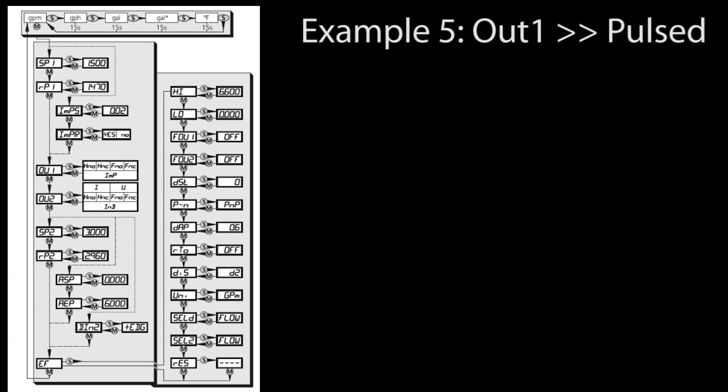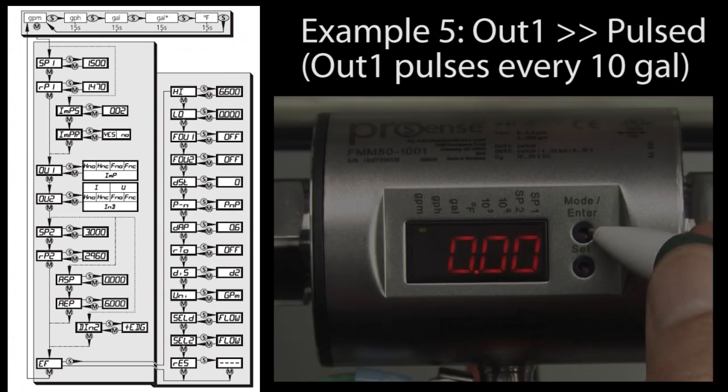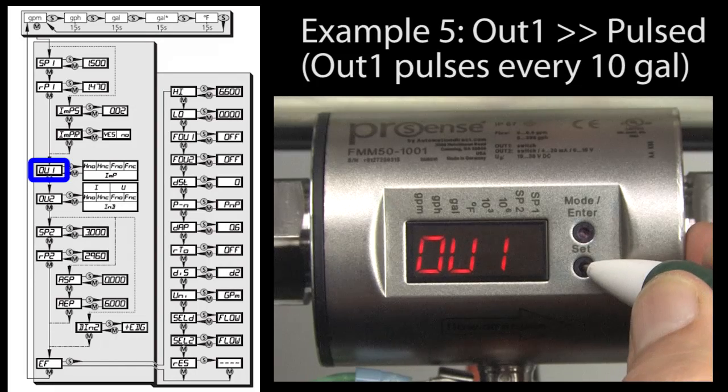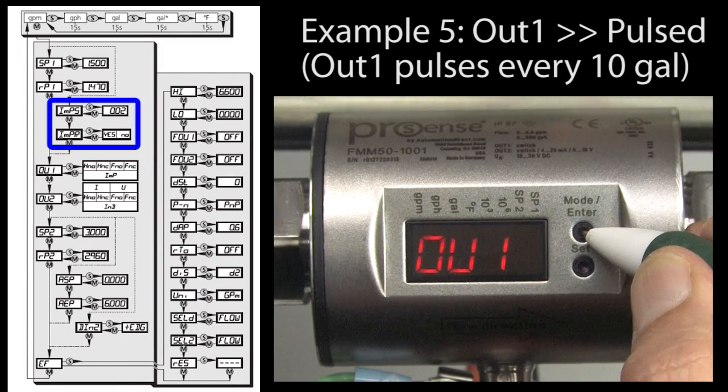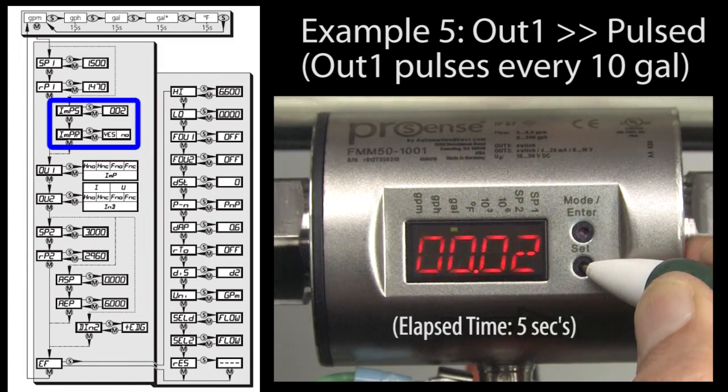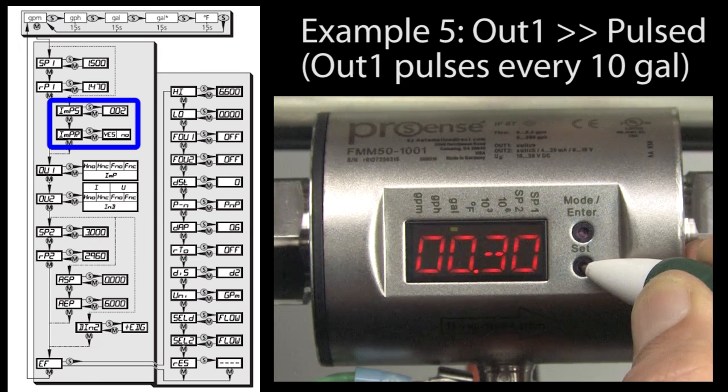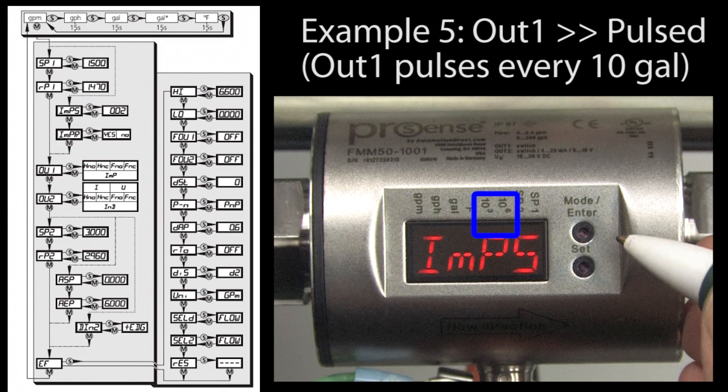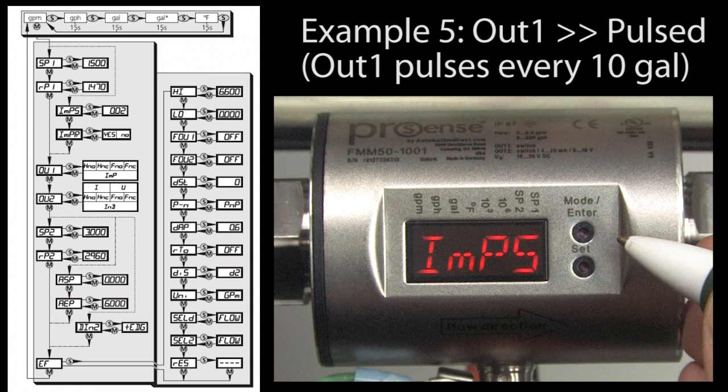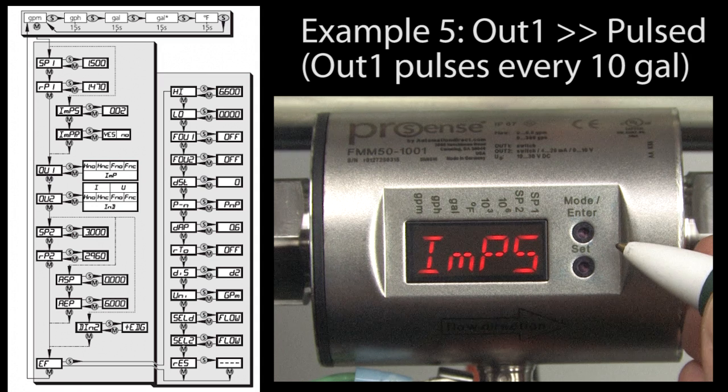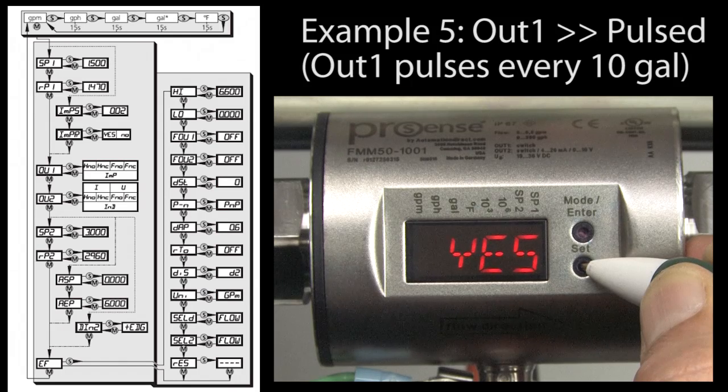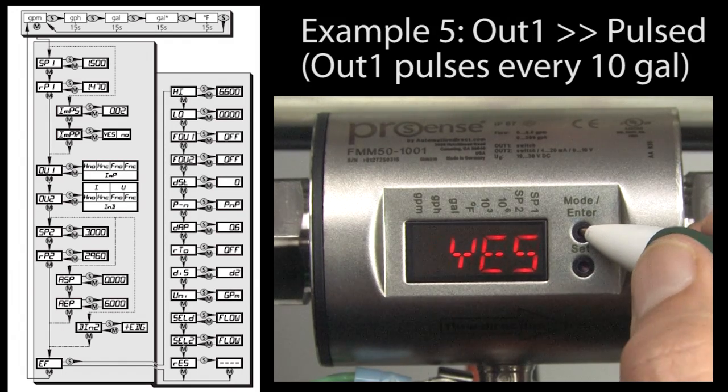Let's do another one. Let's make channel 1 issue a pulse output for every 10 gallons. Select OUT1 and choose impulse. That makes these available. In IMPS you put the number of gallons per pulse. Let's say we want to pulse every 10 gallons. Accept that. If you need larger numbers, these LEDs will turn on to indicate thousands of gallons and millions of gallons after the decimal point has run through all of its possible locations on the display. IMPR is pulse repetition. Do we want just one pulse when the event happens or do we want to pulse every time we get another 10 gallons? Well, we want it to repeat so we select yes.